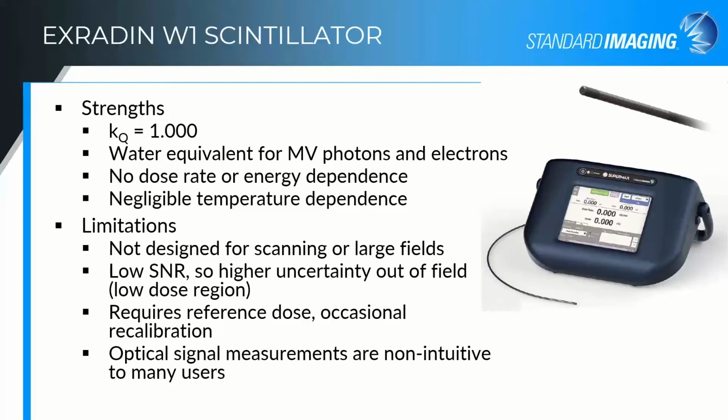It's not an absolute dosimeter as defined by the calibration labs. So you do require a reference dose. You have to cross-calibrate it if you want output in terms of dose. It does need an occasional recalibration as the plastic ages.